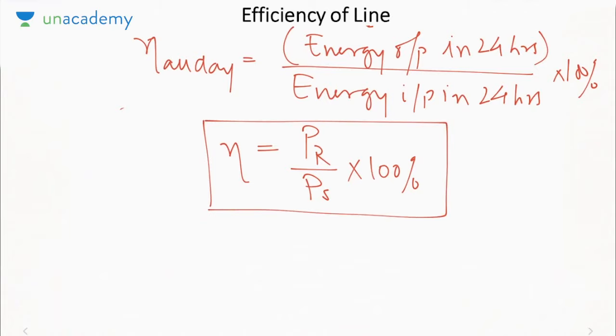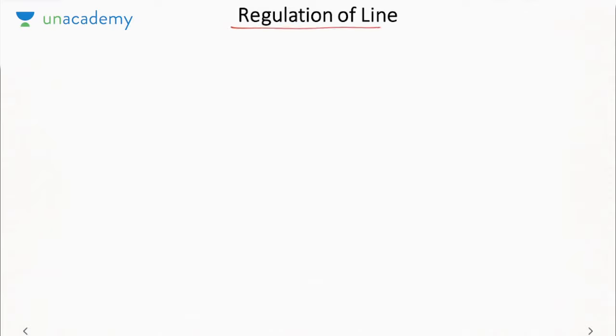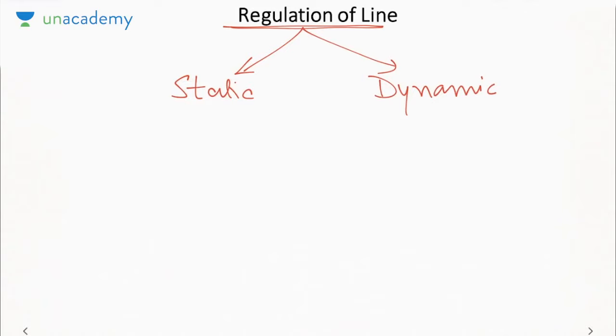The other parameter on which we judge the performance is the regulation or voltage regulation of the transmission line. Now there are two types of regulation. One is called static, the other is called dynamic. So there are two types of system basically when we consider combinedly the electrical machines and the power systems. The systems which have mechanical output, that is your motors. The systems which have electrical output, that is your generators, transformers and transmission line. So wherever there is electrical output, we define static regulation or voltage regulation, because their output is voltage.